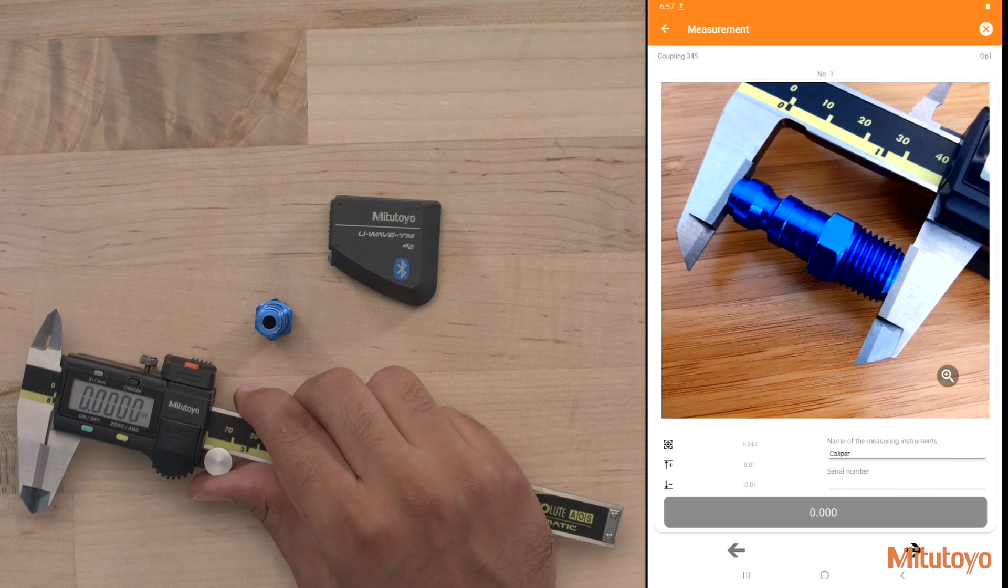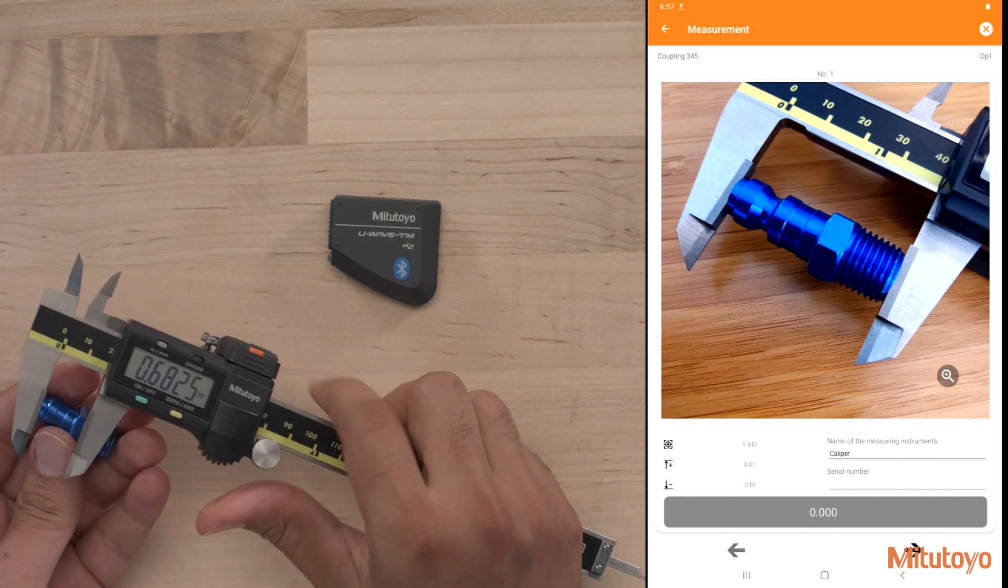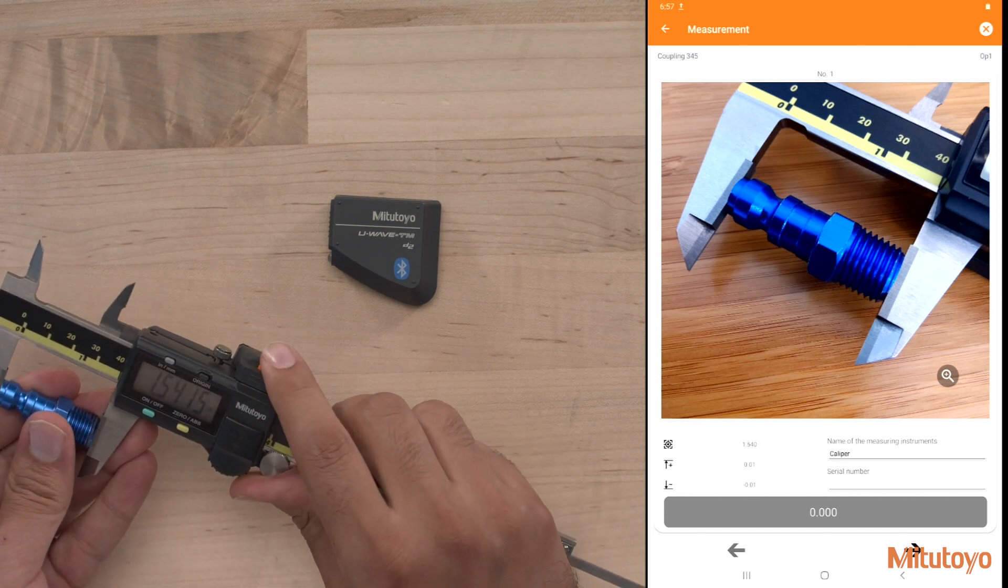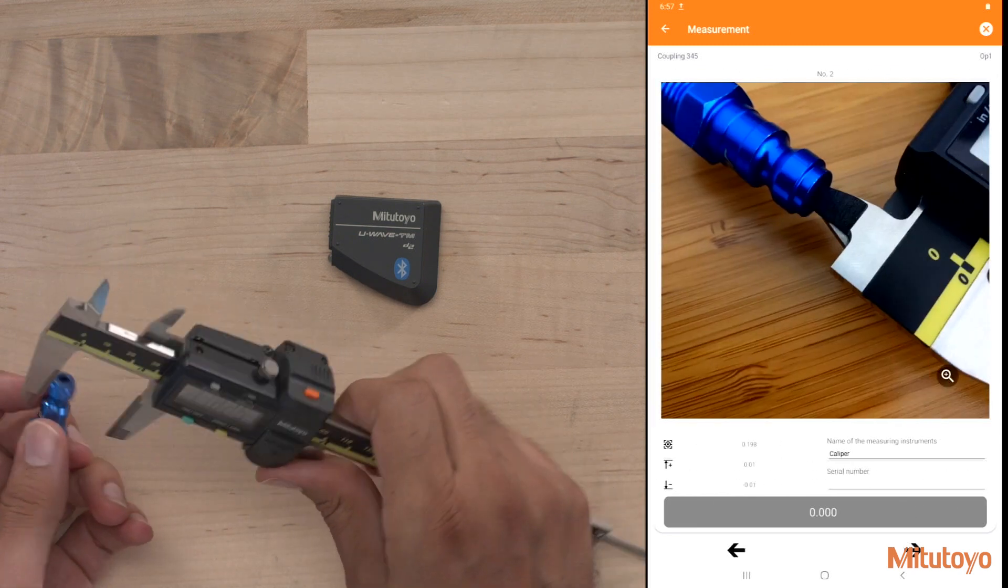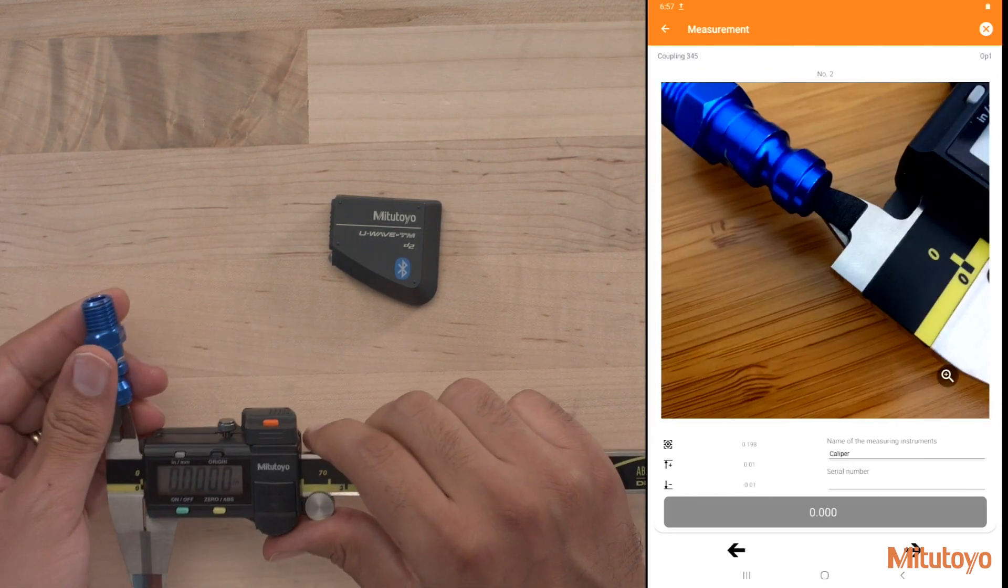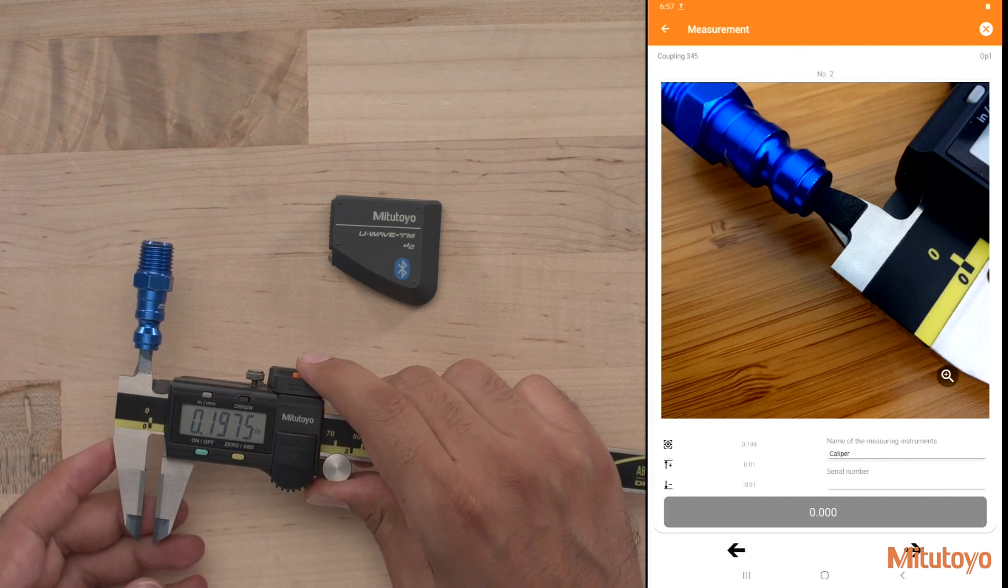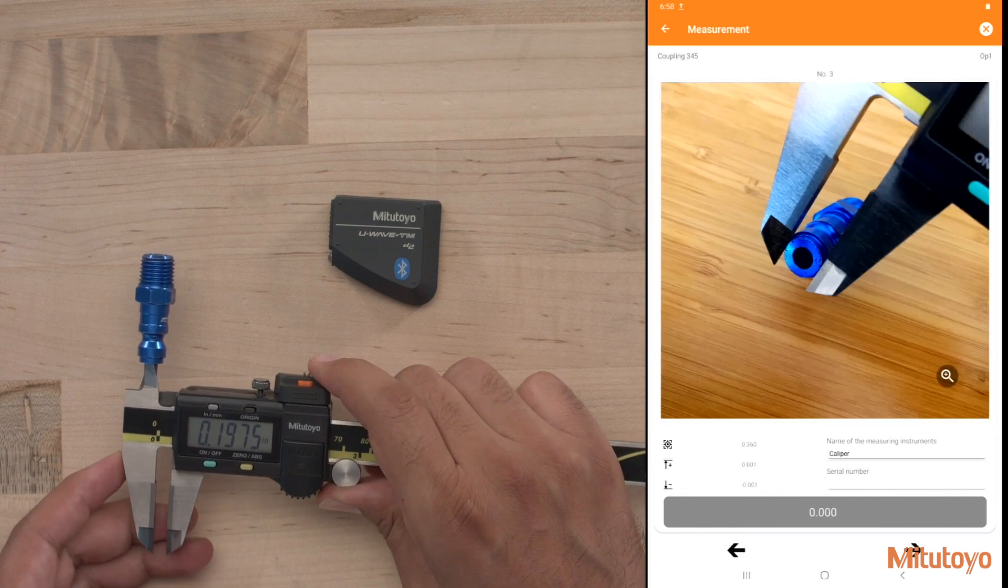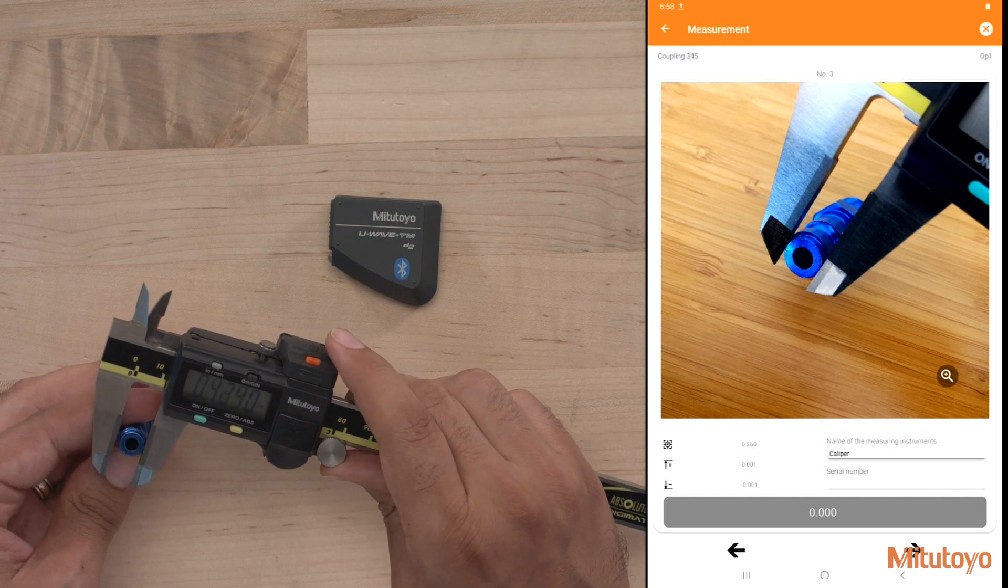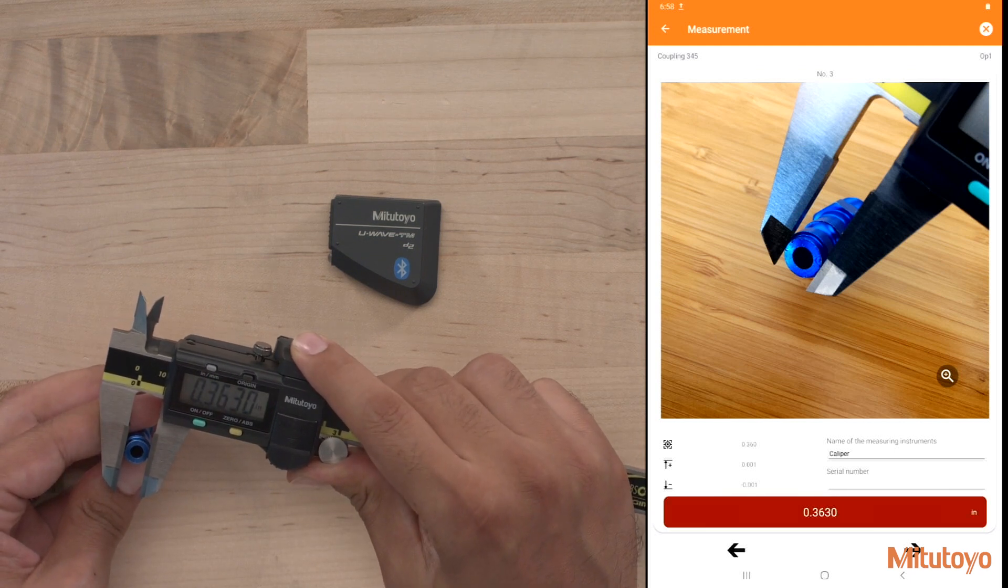So if I'm brand new to measuring this part, I know exactly what's the first thing I'm supposed to measure. I'll go ahead and measure the overall length. Hit the data button. It goes right in and it auto feeds over to the next characteristic. I could use multiple tools. I don't have to use just one tool. So I could have set up a navigation to do all of them. Go ahead and hit the data button here as well. And lastly, I'll go ahead and take my OD. And hit the data button there.